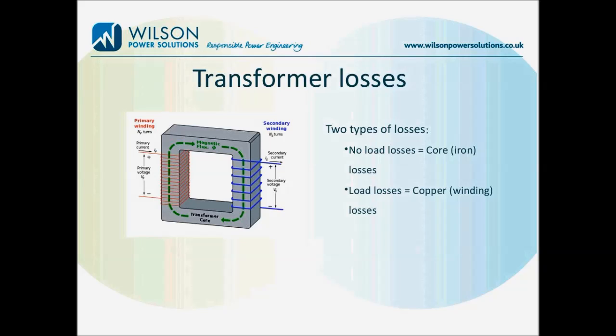There are two types of energy losses when a medium voltage distribution transformer is live. These are load losses and no load losses. The load losses depend upon the varying load of the transformer, but the core losses are fixed, as long as the transformer is energized, which could be 7 days a week and 365 days of the year. I must say at this point, through experience with all our customers, not everybody realizes that when they're metered at medium voltage, they're paying for the losses within their own transformers.